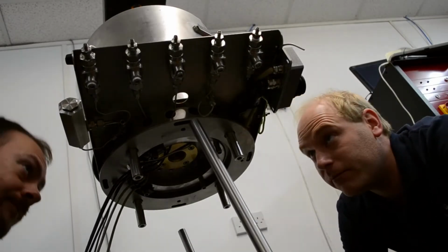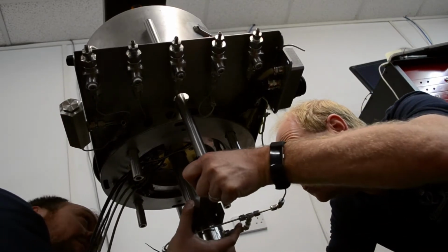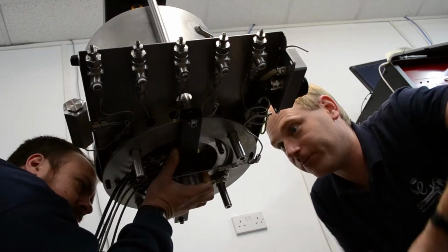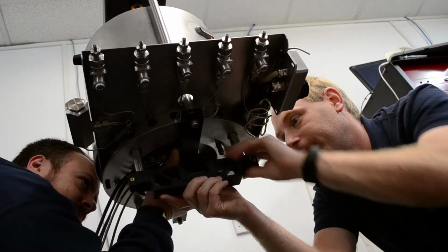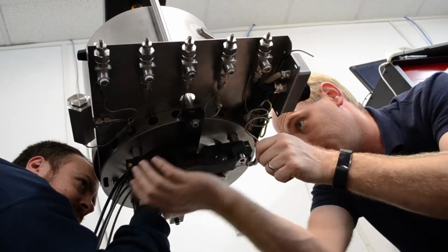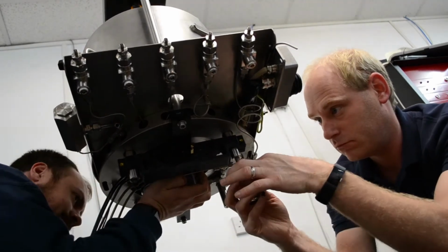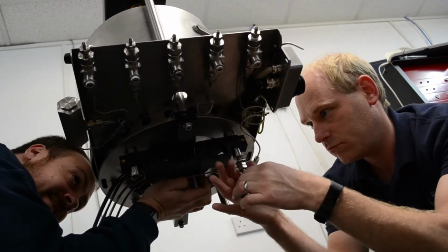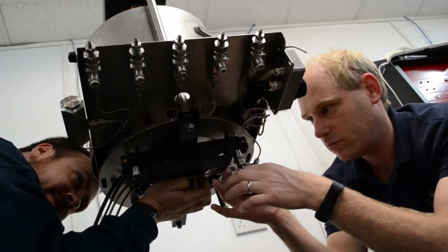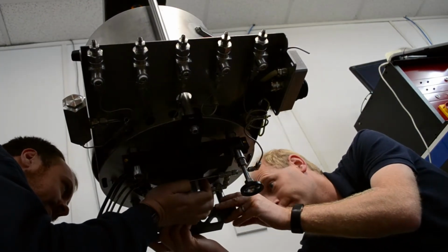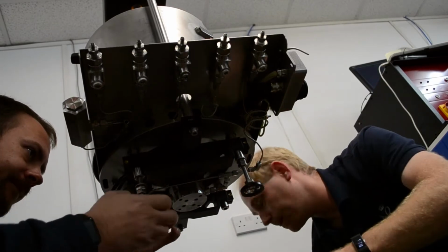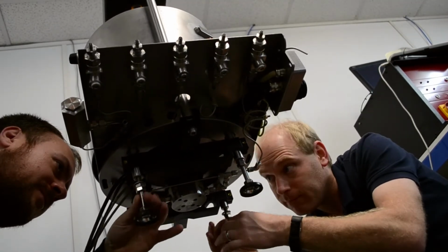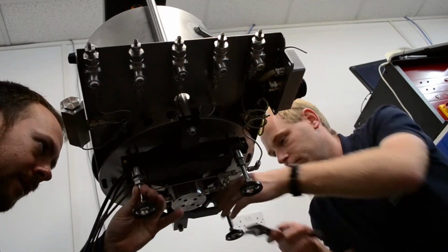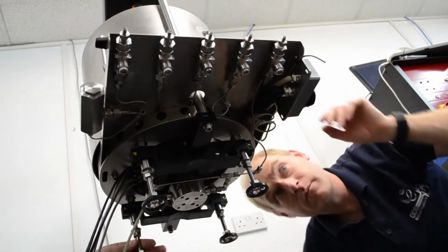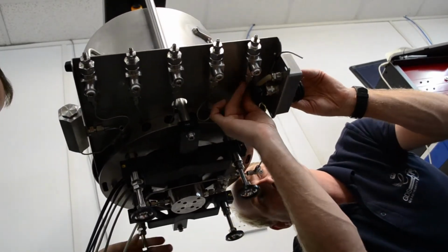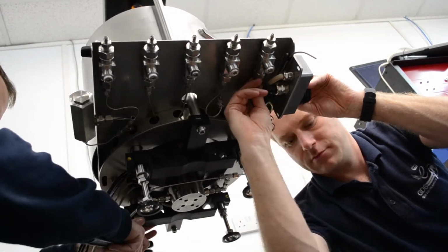Locate the pedestal assembly. If axial displacement transducer bars are fitted, ensure the location of the assembly is correct. Locate the pedestal support bars onto the feet stubs. Screw the feet in place. Use an oversized washer between the feet stub and upper fixing nut to restrain the support bars. If conducting saturated testing conditions, connection of the pipework is required at this stage.